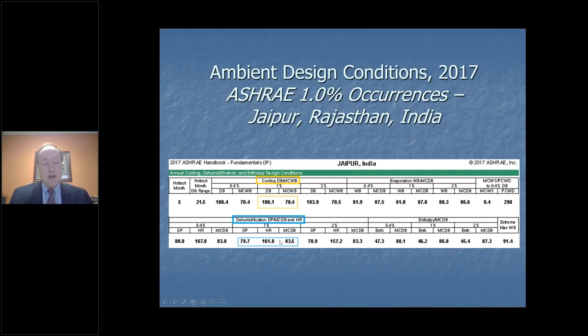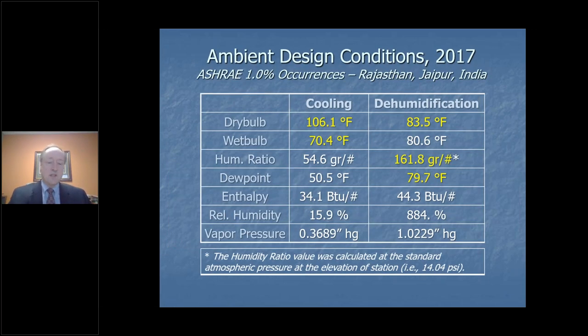So those numbers may not mean an awful lot to you looking at it that way, but if we put it on a chart, pull up your psych chart, maybe you've got this electronically, and you plug in the two numbers from the cooling design point, and it will tell you all of the other numbers that correspond with that on the psych chart. Same thing over here for the dehumidification. You plug in the numbers that are known and then the rest of the numbers you can determine from your psych chart. Or if you look at it from the psych chart, here's what you see.